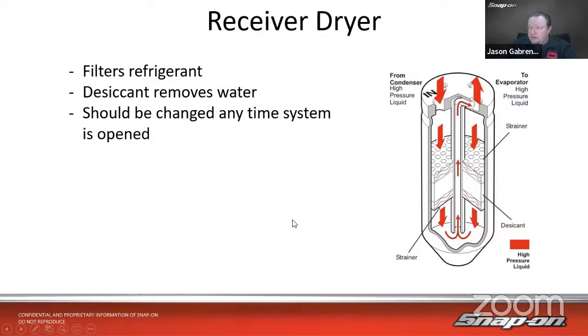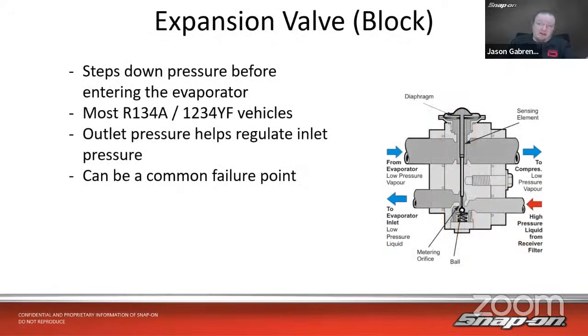Well, the receiver dryer, that filters the refrigerant. So if there's any impurities in there, it tries to filter them out. There's a filter in here. There's also desiccant, which helps to remove any water that might be in the system. So you could get water in the system a few different ways. This also should be changed out anytime the system is open. So if I open it up and introduce air, ambient air into the system, there's going to be humidity in that air. There's going to be water vapor in that air. So it is usually recommended to be changed at the time when I do any other sort of AC work as well. And then we have the expansion valve.